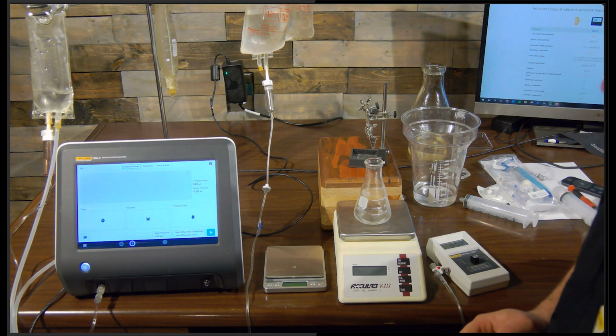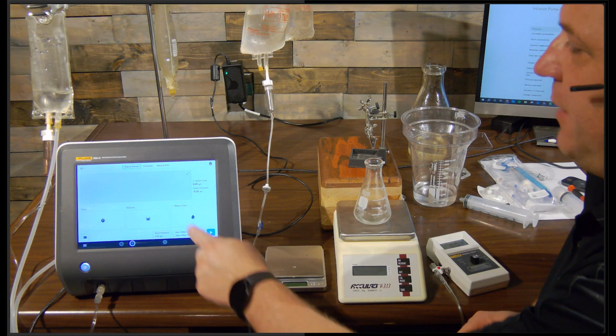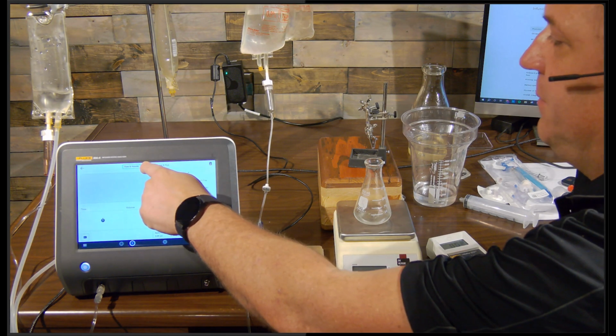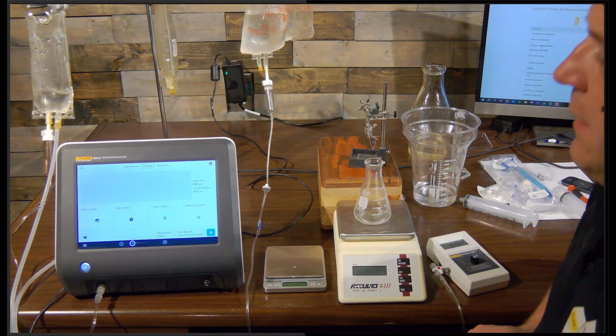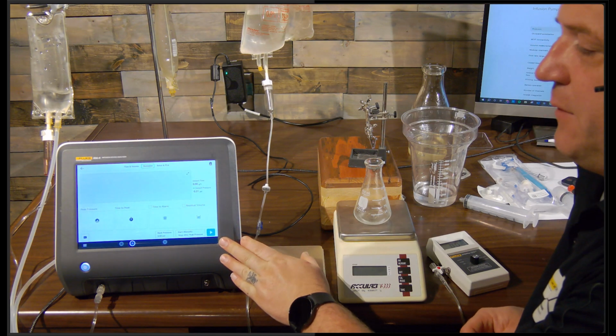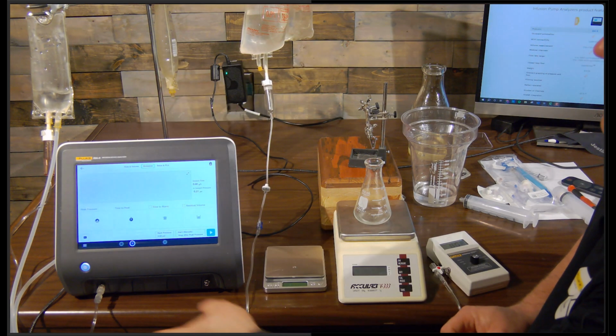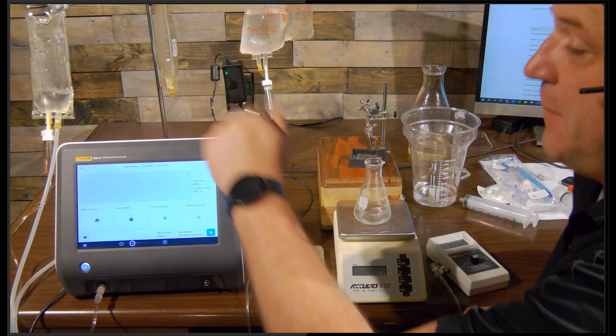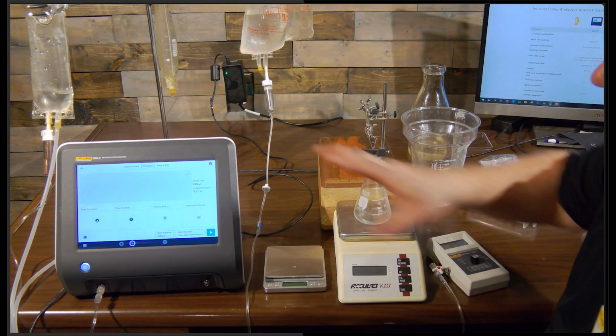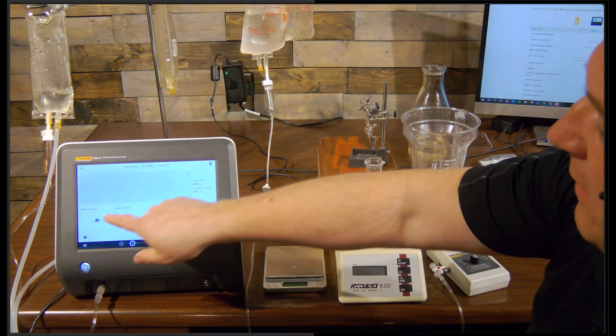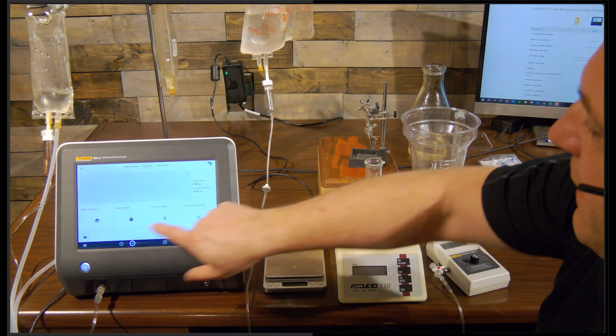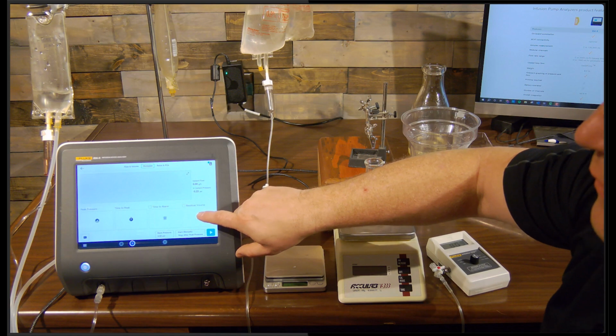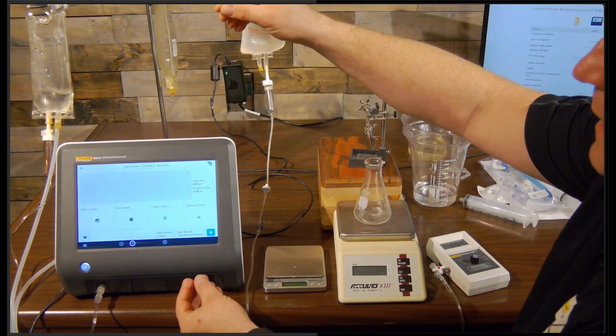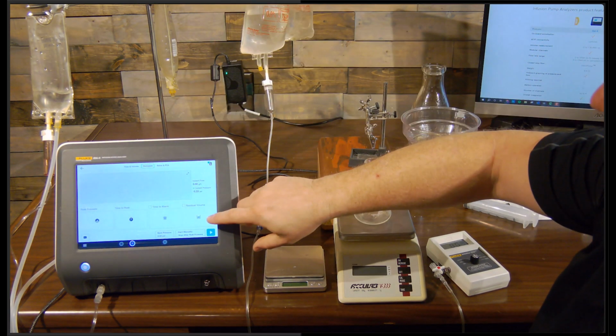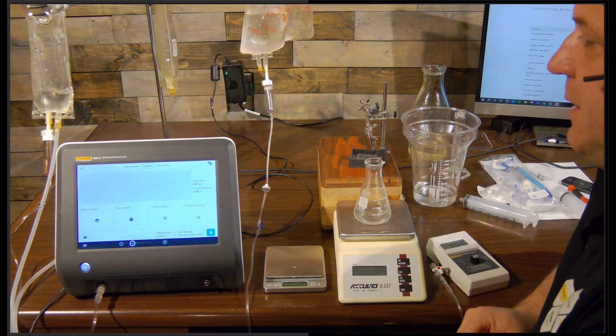And when I need to do my occlusion test, I would hit stop on this, push occlusion, and I could run my occlusion test right through this as well. Do the priming cycle, push play, and it catches my peak pressure for me. This is set up so that it will catch that peak pressure, and it'll mark it, and then I'll have my peak pressure, time to peak. If I needed it or wanted it, I could get the residual volume. So after it releases the occlusion pressure, the volume that comes out afterwards. So this is really nice.